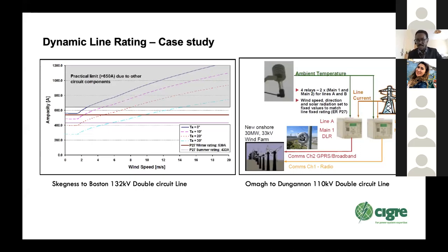The other case study, which was conducted by NIE, was done to prevent an overload of the Omagh to Dungannon 110 kV line. In this case, a relay was placed at a 30 megawatt wind farm, because the wind farm was the critical factor in deciding whether or not the line was going to be overloaded. The data from the dynamic line rating sensors was fed to the relays, and using an algorithm, they were able to decide whether or not, under certain scenarios, they could cut off the connection between the farm and the line. So you can see that dynamic line rating can be used for several different purposes, both for increasing the capacity of the line and for protecting the lines and preventing overloads and other cases such as this.